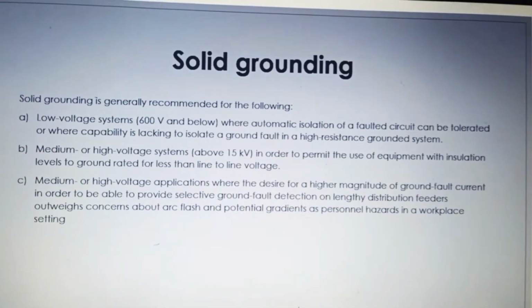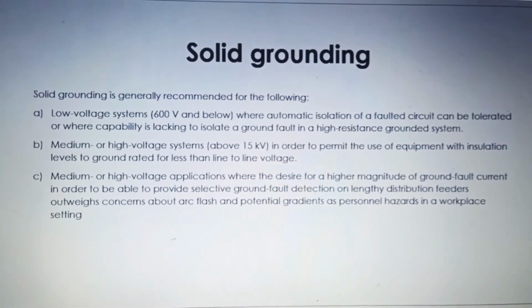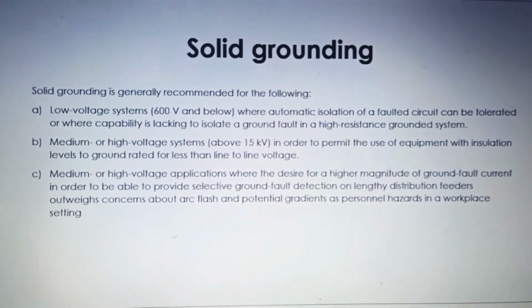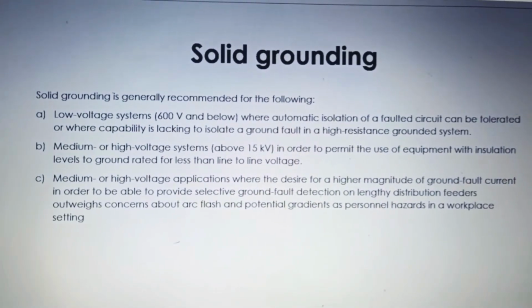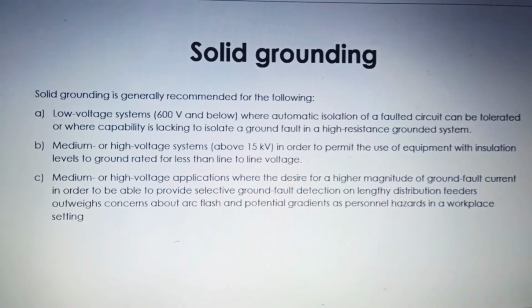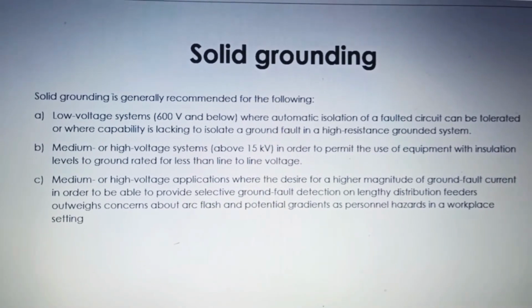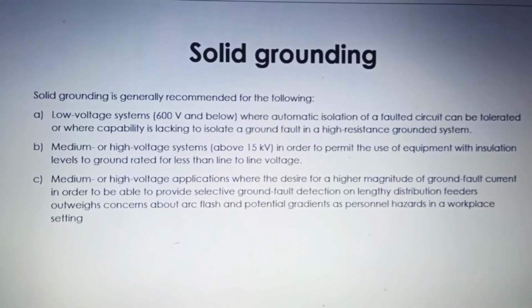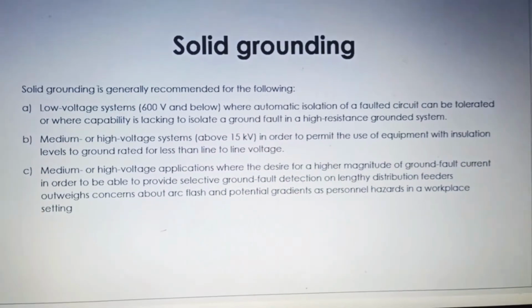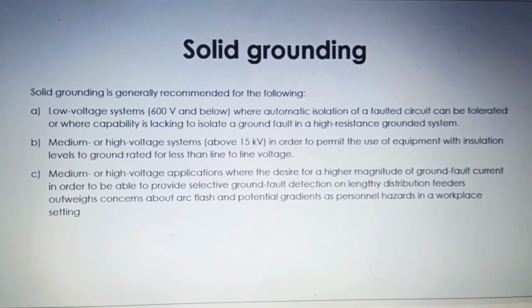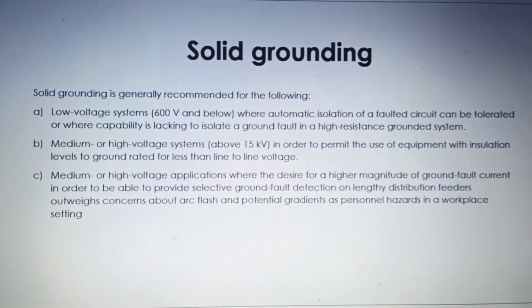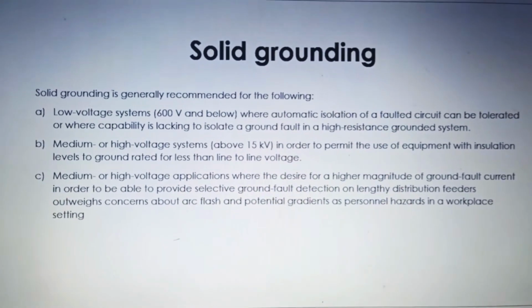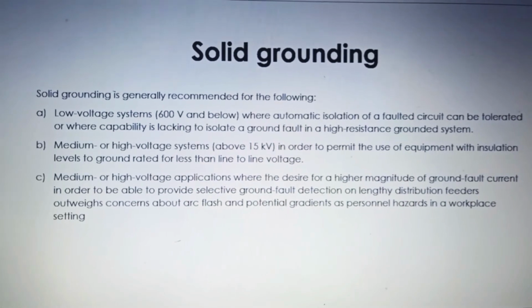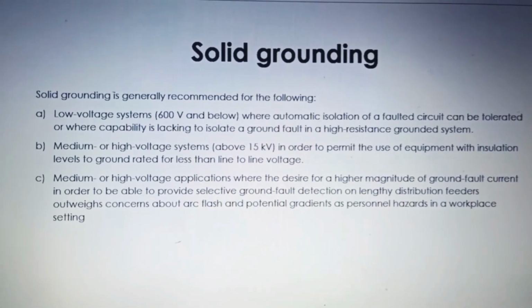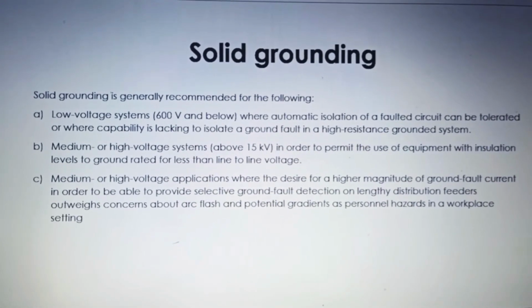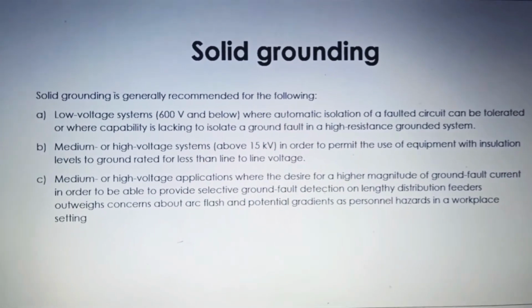Solid grounding is recommended for low voltage systems, which is 600 volts and below, where automatic isolation of the faulted circuit can be tolerated, or where capability is lacking to isolate the ground in a high resistance grounded system. It is also recommended for medium or high voltage systems, which is above 15 kilovolts, in order to permit the use of equipment with insulation level ground rated for less than line-to-line voltage.